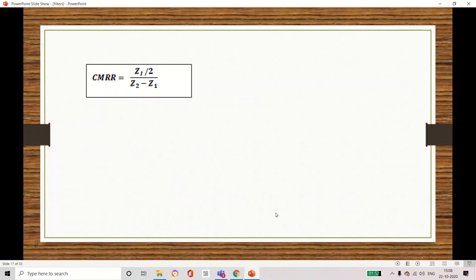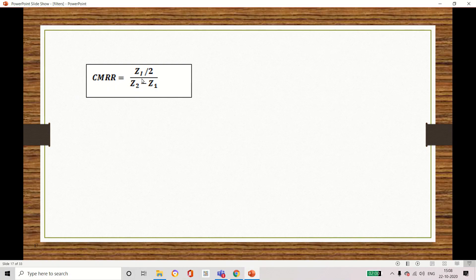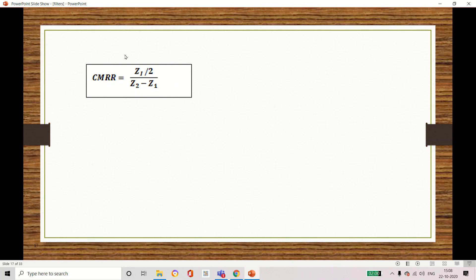The problem is due to imbalance in the source impedance, which is why we use this impedance matching circuit. To avoid this imbalance, we can increase the input impedance and increase the CMRR — two options. From the formula, we can understand that if you increase the input impedance or reduce the difference between skin contact impedances, the CMRR value will automatically increase.